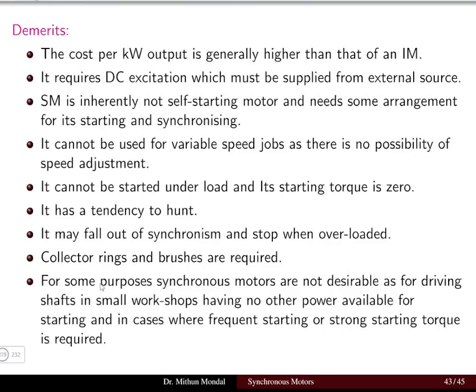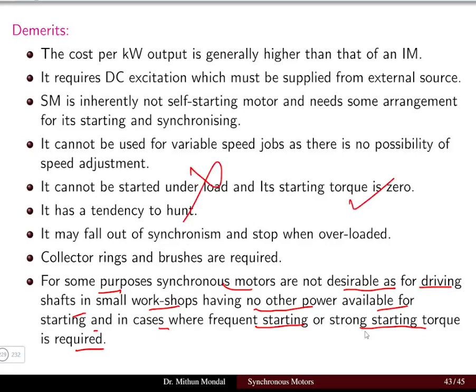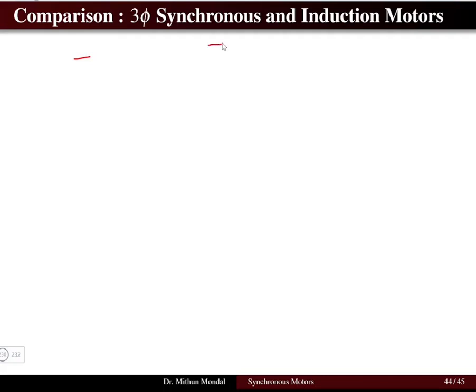Collector rings and brushes are required, which are costly and increase the price of the synchronous motor. For some purposes, synchronous motors are not desirable — such as driving shafts in small workshops with no other power available for starting, or where frequent starting or strong starting torque is required.